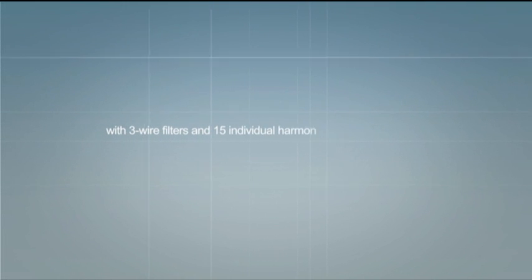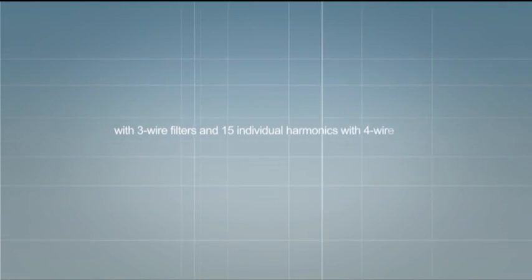But the PQF has much more to offer. Filtering of harmonics up to the 50th order. Simultaneous filtering of 20 individual harmonics with 3-wire filters and 15 individual harmonics with 4-wire filters. Target limits for each harmonic can be preset.